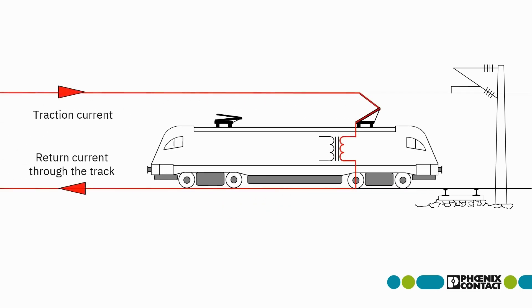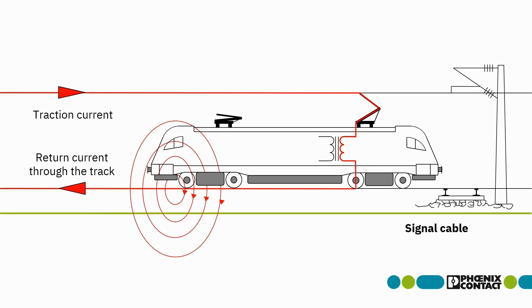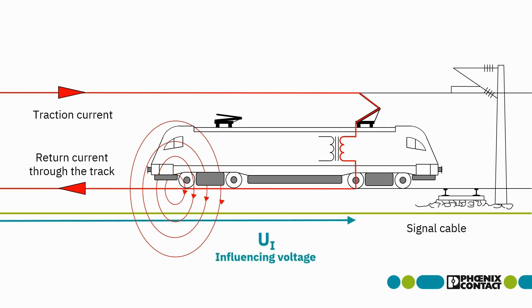In electric traction, the current flows through the overhead line to the traction unit and through the track, and partly back to the earth. This creates a magnetic field. Signal and telecommunication cables are laid next to the track, and the influence voltage is induced in these cables.